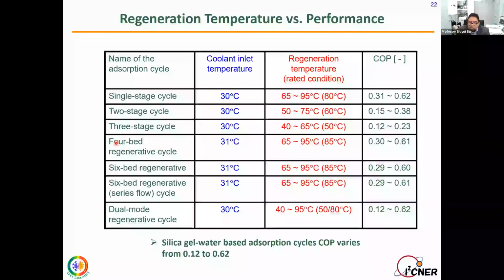Then we have 4-bed regenerative cycles, from which we can get a little bit higher COP values. And finally, I showed the performance of the dual mode cycles. It can operate from 40 to 95 degree heat source temperature. In the single stage mode, usually 80 degrees is the rated condition. For 3-stage mode it is 50. And then COP varies from 0.12 to 0.62.